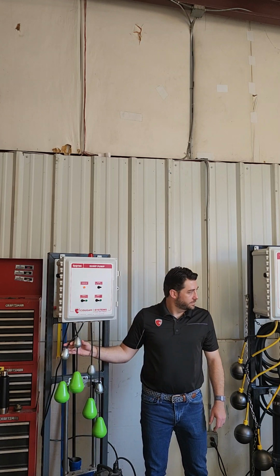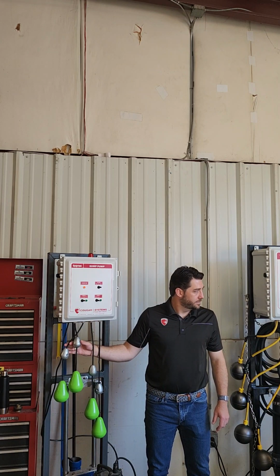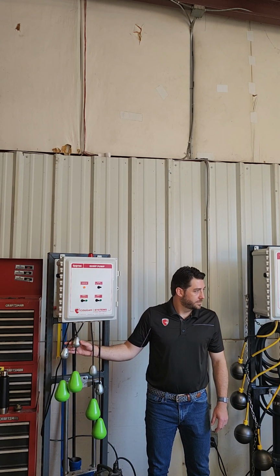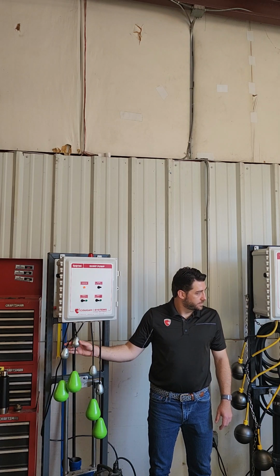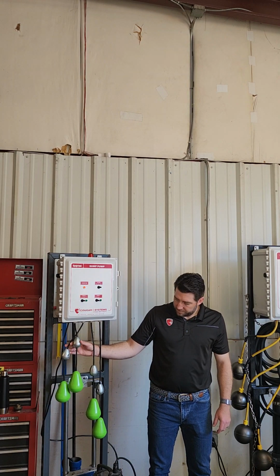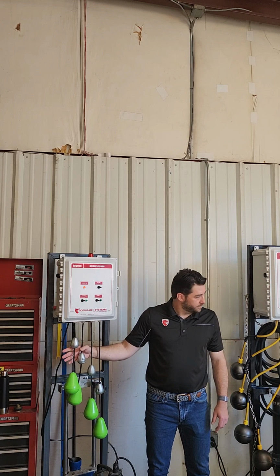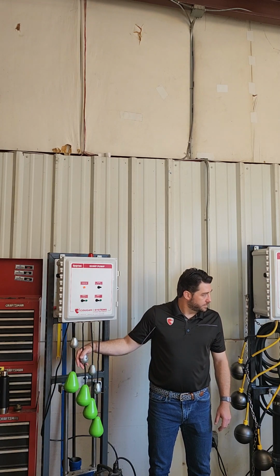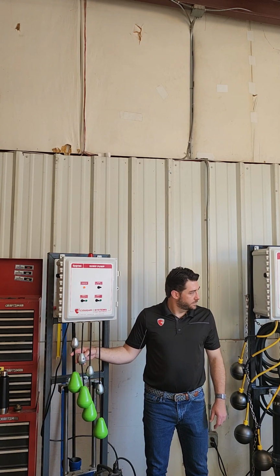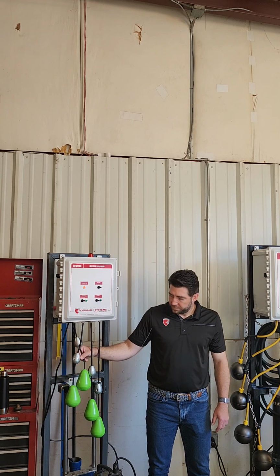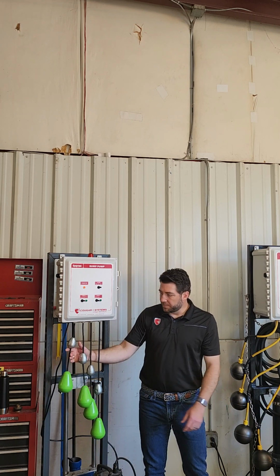So if one pump fails, it gets locked up or whatever, it sends you an alarm to let you know that there's an issue, but you still have the second pump to be able to pump it down. Because on that normal standard, you won't get an alarm until both pumps are locked up. Yeah. So you want to make sure you get an alarm before, and that's how we do that. Yeah, so you can put them in a different order.